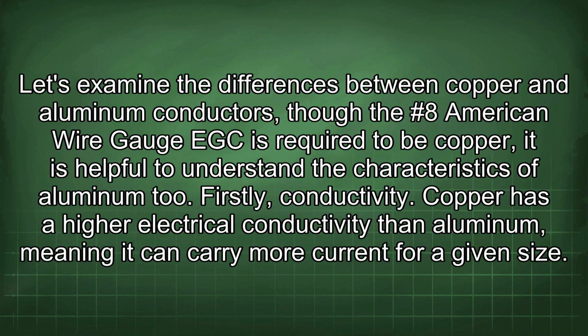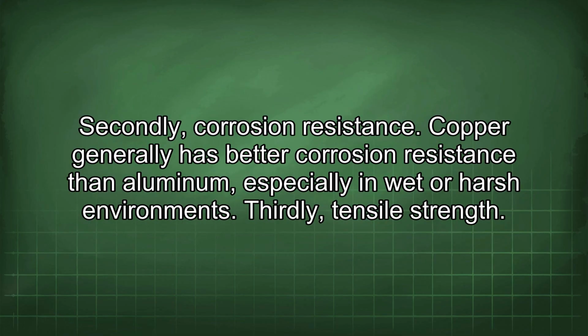Let's examine the differences between copper and aluminum conductors. Though the #8 American wire gauge EGC is required to be copper, it is helpful to understand the characteristics of aluminum too. Firstly, conductivity. Copper has a higher electrical conductivity than aluminum, meaning it can carry more current for a given size. Secondly, corrosion resistance. Copper generally has better corrosion resistance than aluminum, especially in wet or harsh environments.